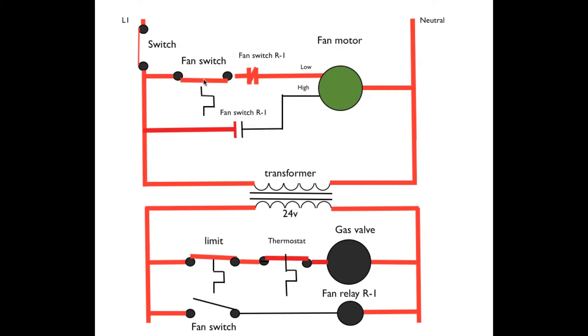Okay, the next thing that's going to happen is the heat operated fan switch is going to close. This fan switch is closed as the heat exchanger warms. Power is going to pass through the normally closed R1 fan switch contacts to energize the fan motor. So at this point, gas valve is energized, warmed up the furnace, fan switch is closed. Power passes through the normally closed set of fan switch contacts and energizes the motor in low speed.